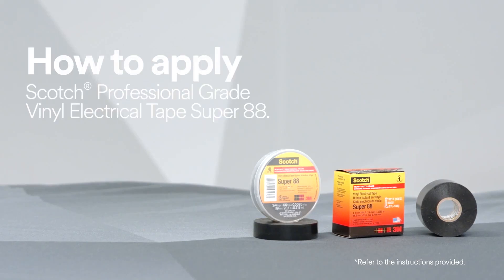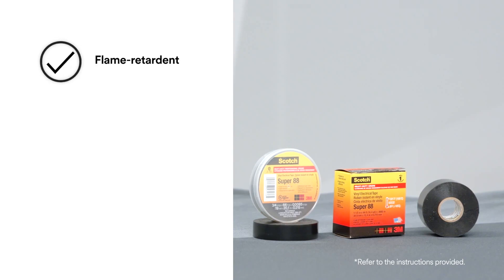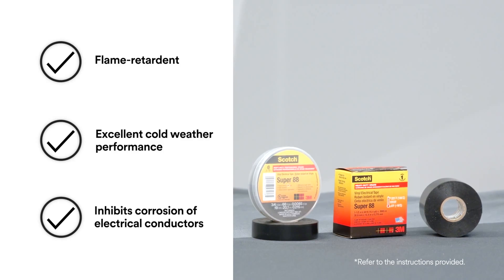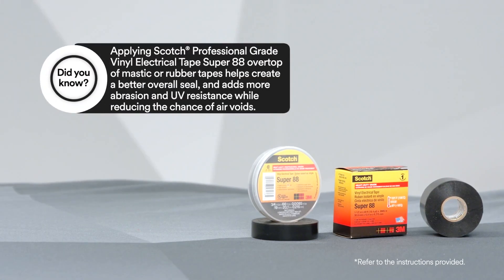To help protect against abrasion, chemicals, and UV radiation, use Scotch professional grade vinyl electrical tape Super 88. Not only can it be used as low voltage primary insulation (less than 600 volts), but the extra thickness and vinyl makeup will enhance and protect in many electrical applications.